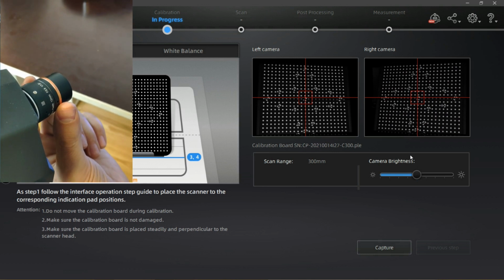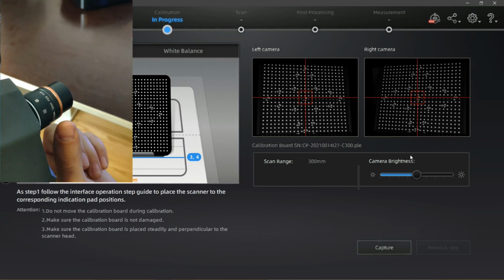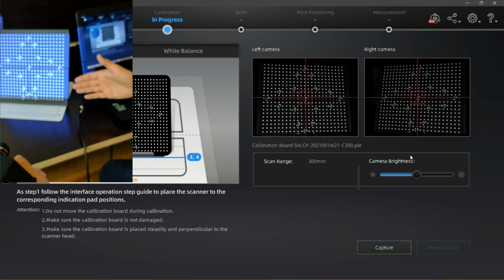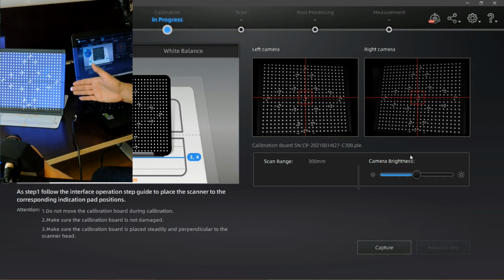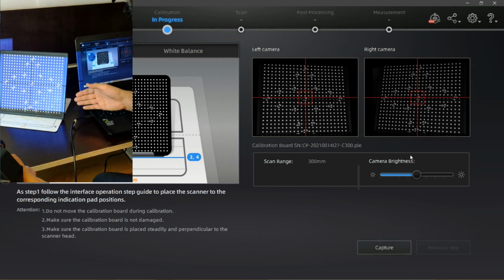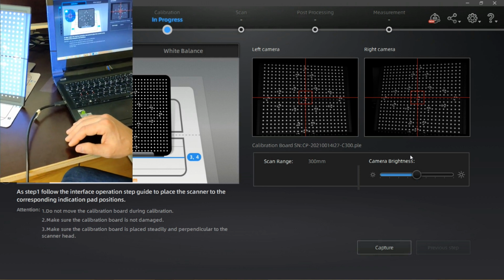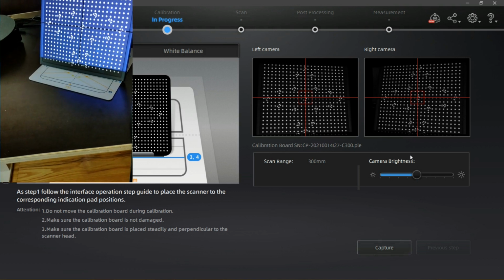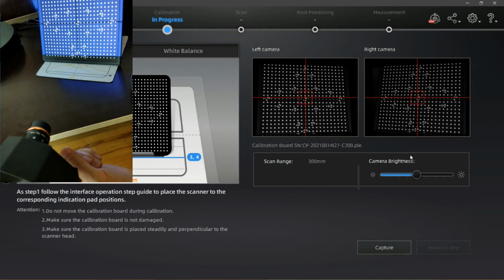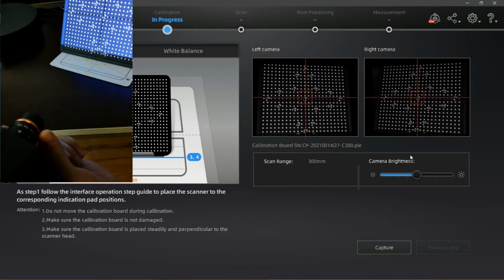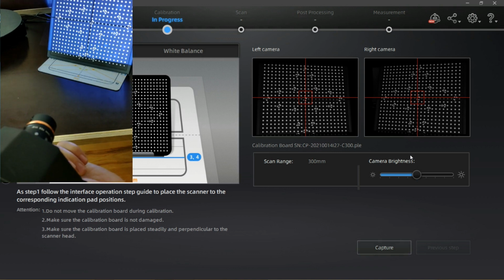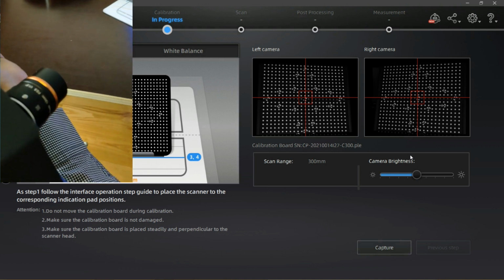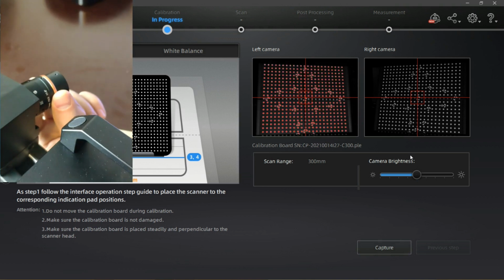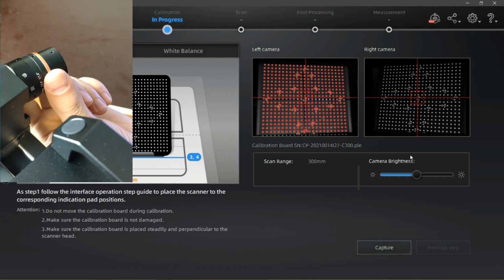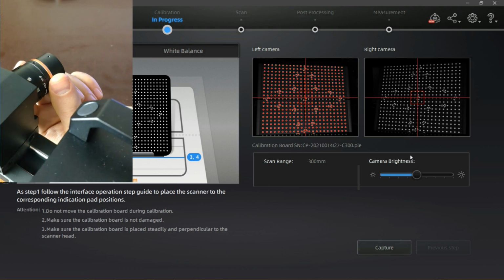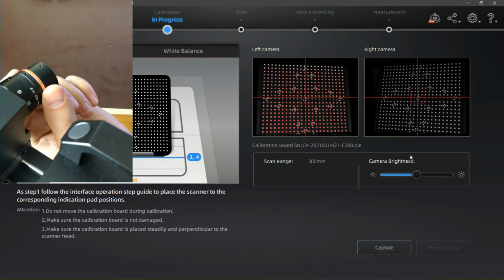Just expect that you will change the distance to your scanning system from the calibration board. That will have a big influence on the amount of light that will be reflected. So the light density or intensity on your calibration board coming near will rise up very fast. That's not linear. So don't go to the very uppest level that you can have on brightness and sensitivity. Both sides should look similar. I'm just going back on the other side as well.